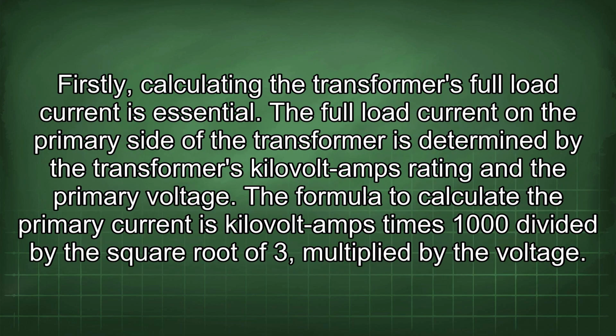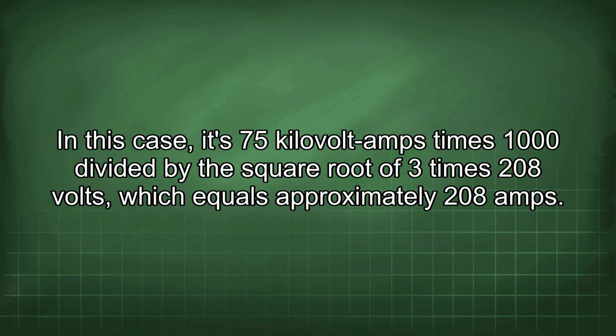Firstly, calculating the transformer's full load current is essential. The full load current on the primary side of the transformer is determined by the transformer's kilovolt-amps rating and the primary voltage. The formula to calculate the primary current is kilovolt-amps times 1000 divided by the square root of 3 multiplied by the voltage. In this case, it's 75 kilovolt-amps times 1000 divided by the square root of 3 times 208 volts, which equals approximately 208 amps.